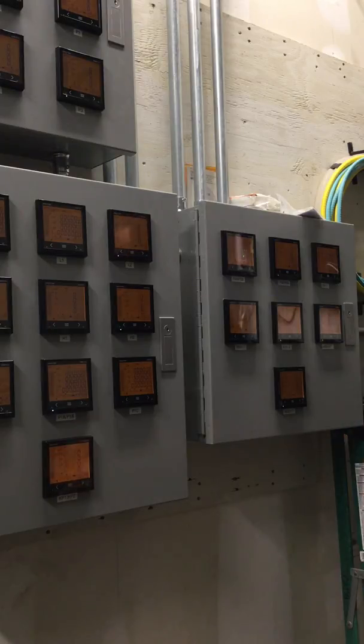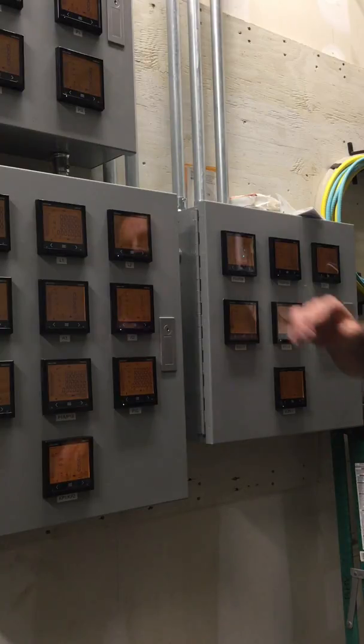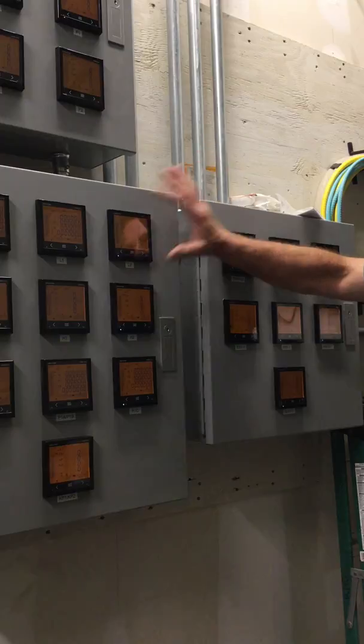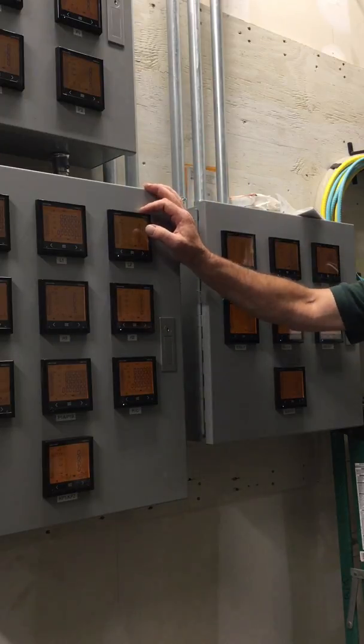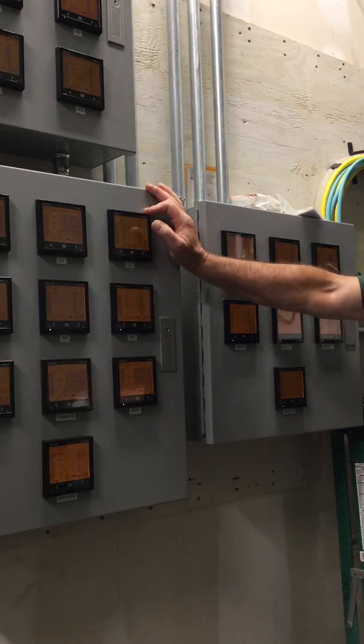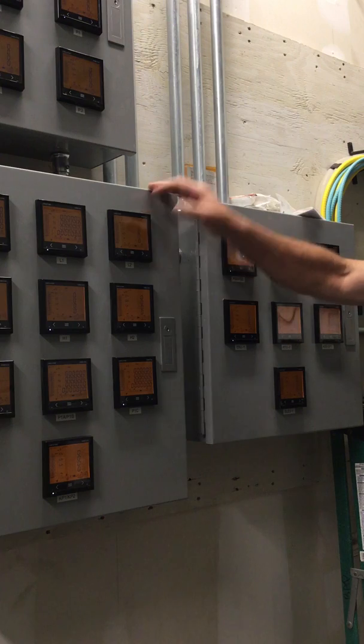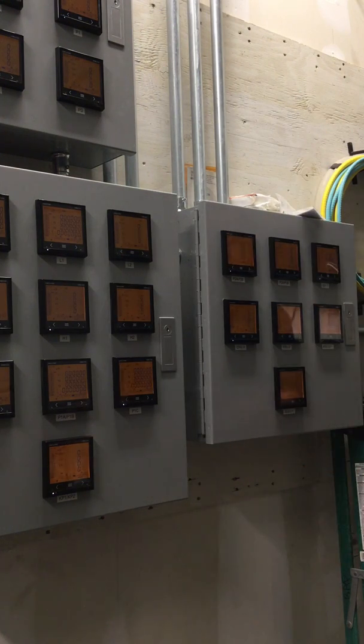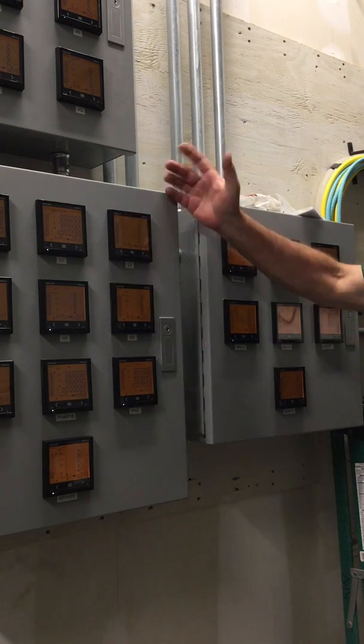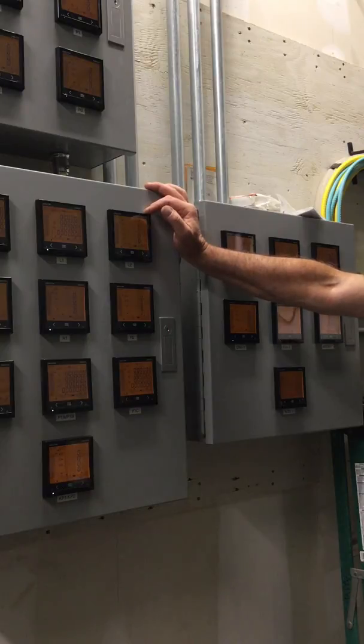What do these run off of? Current sensor? Current transformer, okay. 5 amp secondary. So if the meter was programmed for 200 amps because it was a 200 amp load, it probably has a 200 to 5 on it, 400 to 5, 2000 to 5 current transformers. The reason is the utility standard is 5 amp CTs, so everybody kind of uses them in the sub-metering world, except one company.